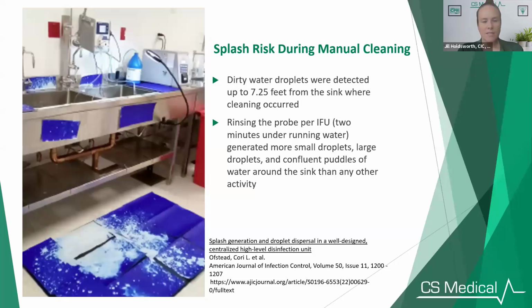So some of these rooms that I have seen, where ultrasound probes and TEE probes are being cleaned, aren't even that big. So that means that this water that has detergent, microbes, all sorts of things is all over that room. And that also means it's all over the person. It's all over the clean probes if they're being stored in there. So some of you have your clean probes hanging on hooks in these tiny rooms. And so this water and all these microbes are splashing all over the place. Some of you are cleaning your probes in the clinic rooms and patient rooms. So that means you're splashing on the equipment and the patient exam table or the bed. So this is a huge risk. This is a risk to not only you as the reprocessor, this is a risk to the patient equipment, the patient room. So this concerns me a lot.